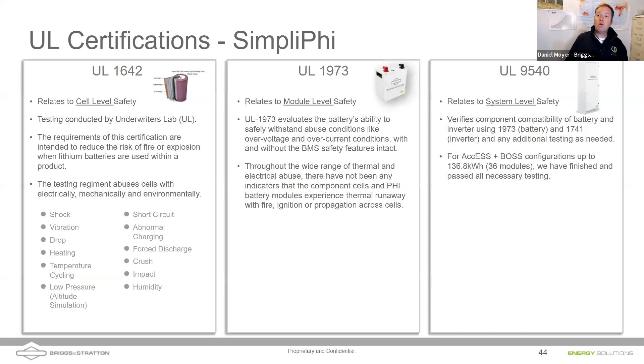Then what we did is finally took those battery modules or batteries and put them into a battery system. The system uses a listed inverter, a 1741 inverter, and our 1973 batteries, puts them into a system. Then what we have to do is pass our UL 9540A. The UL 9540A is not a pass/fail, it's not a certificate.